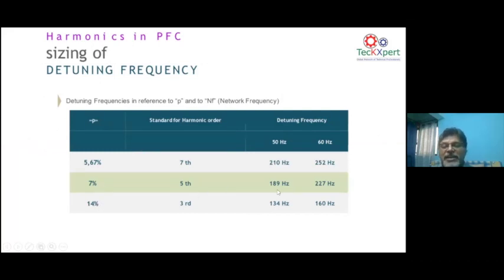But when you detune it, you are bringing a new natural frequency in the circuit. For example, if you put a 7% detune reactor, the natural frequency of the capacitor with the rest of the inductance becomes 189 hertz. You don't have a harmonic at 189 hertz. You will either have 150 hertz or 250 hertz, third harmonic or fifth harmonic. So 189 hertz does not cause any resonance. That is how we detune it and protect the capacitor bank against resonance.